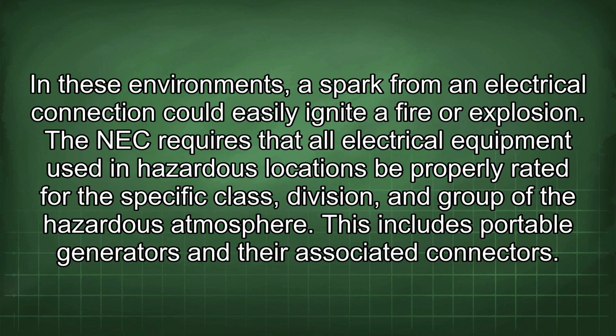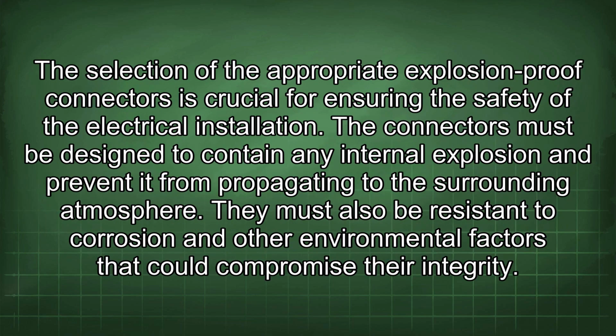The NEC requires that all electrical equipment used in hazardous locations be properly rated for the specific class, division, and group of the hazardous atmosphere. This includes portable generators and their associated connectors. The selection of the appropriate explosion-proof connectors is crucial for ensuring the safety of the electrical installation. The connectors must be designed to contain any internal explosion and prevent it from propagating to the surrounding atmosphere. They must also be resistant to corrosion and other environmental factors that could compromise their integrity.